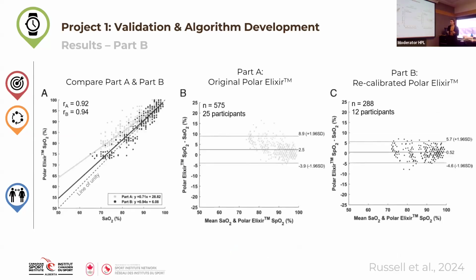Correlation and Bland-Altman plots again. The gray data points and line on that correlation plot, as well as the gray Bland-Altman plot, are the exact same correlation and Bland-Altman plots as the part A ones before, just rather than in blue, green, red, just in gray to compare the two. So we can see that the black data points and black line of best fit are the part B recalibrated signal, and it's closer to that line of unity, especially at those more hypoxic ranges, which is great. And our Pearson correlation coefficient got slightly better from 0.92 to 0.94.